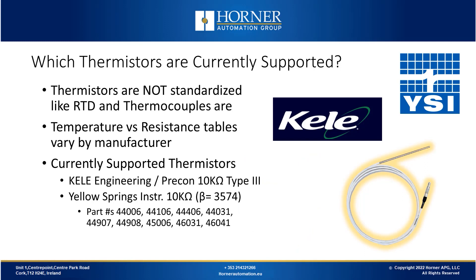Now we'll look at which thermistors are currently supported. As we've seen, thermistors are not standardized in the same way that RTDs and thermocouples are, and the resistance versus temperature tables can vary by manufacturer. We support a few brands that have been around for a long time. Starting with Kele Engineering, we support their Pre-Con 10K ohm Type 3 thermistors. From Yellow Springs Instruments, we have some 10K thermistors that are also supported, with part numbers listed on the chart.